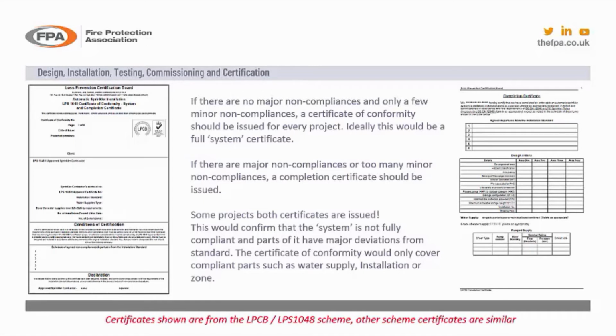So were there any agreed deviations or non-compliances? If you've got minor non-compliances, you may still get away with issuing a certificate of conformity on the left hand side. What we want to remember is that these certificates are issued under licence by the contractor from their third party scheme providers. So they issue them. They can't be bullied into issuing them if they aren't compliant. They must be issued correctly.